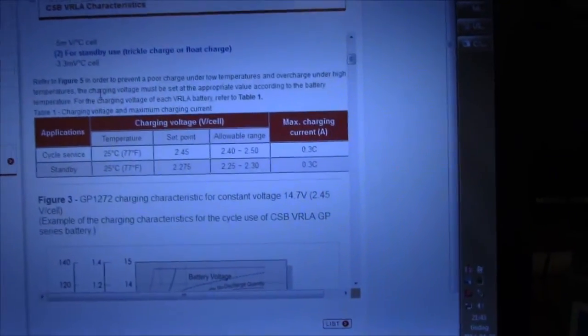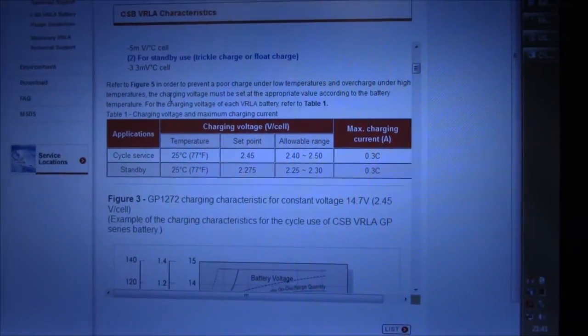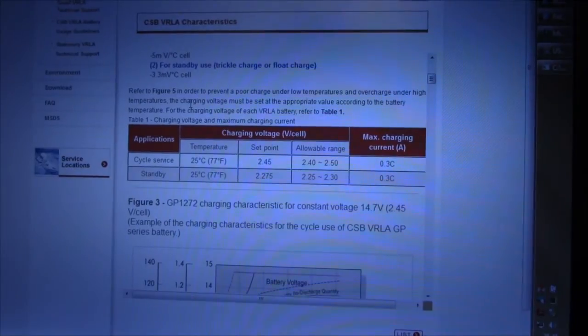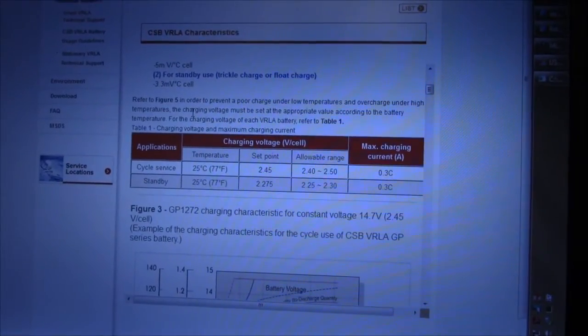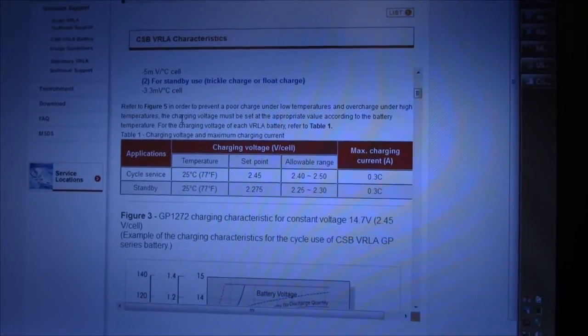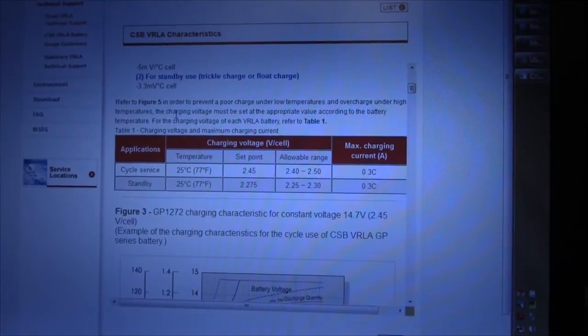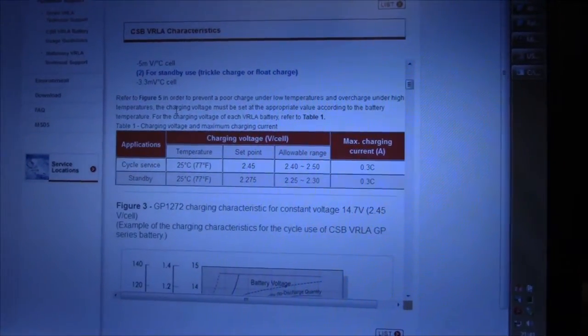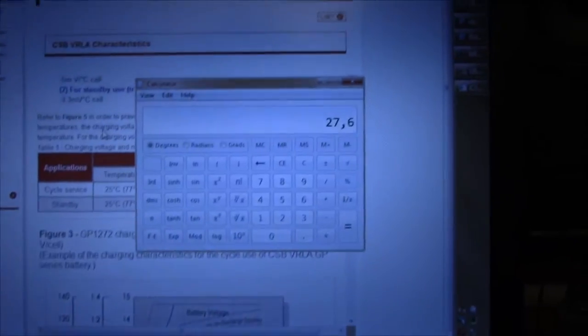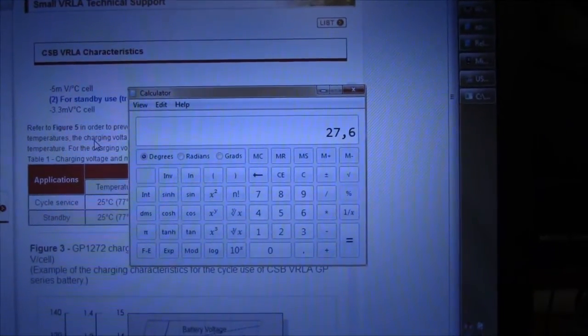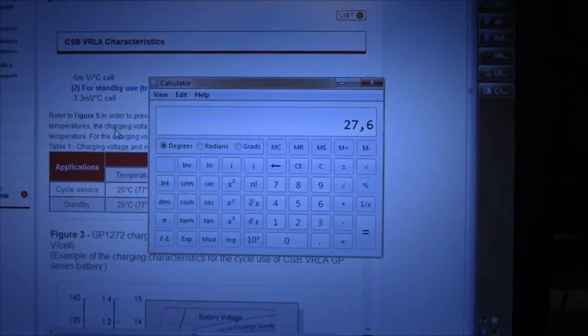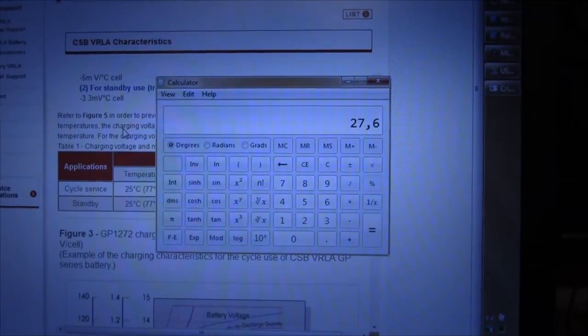The company which thankfully has a website. And looking up the specifications for the standard issue UPS batteries, you're quoted with a maximum voltage of 2.3 volts per cell, which equals to 27.6 volts for a 24 volt pack. And that's on the high side.